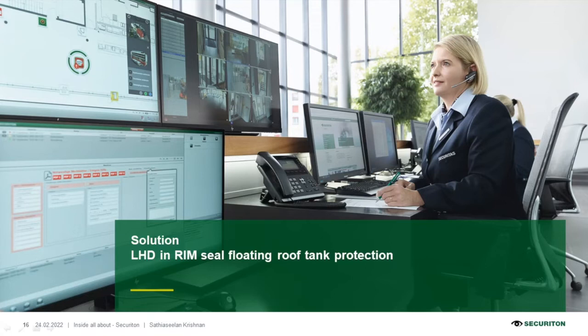And will lightning cause any issue for installation, since this is mainly an outdoor application? Yes, it does give you an issue. As I mentioned earlier, one of the issues from the research paper, lightning and heavy rains also cause issues on the applications installed. So we have the right precautions, which I'll be explaining in the solution part, where you need to put it into a weatherproof box as well as an explosion-proof box, and you have an insulator, whereby we can use copper together with the hard plastic tube in a combination where static will not pass through from the copper coil or the stainless steel towards the LHD. Any other questions?